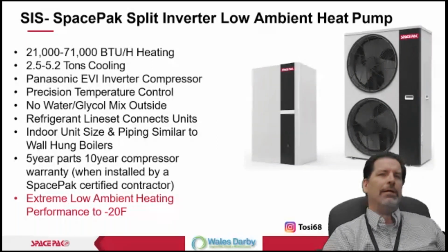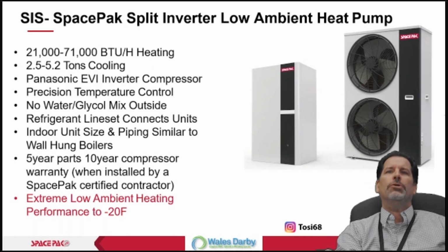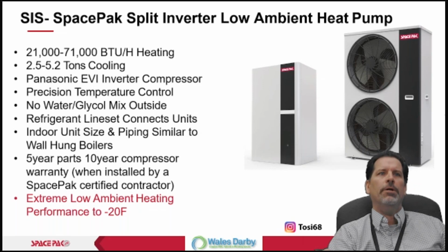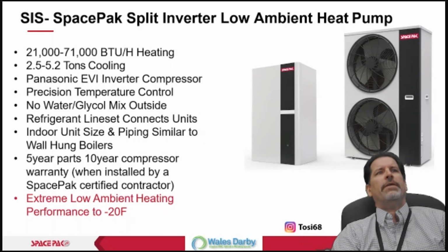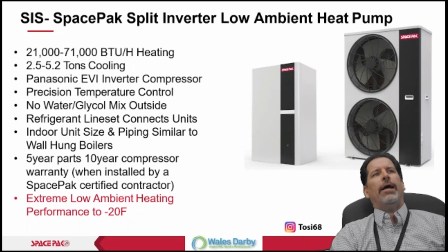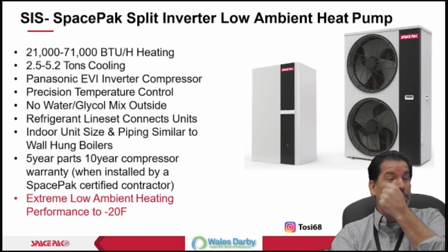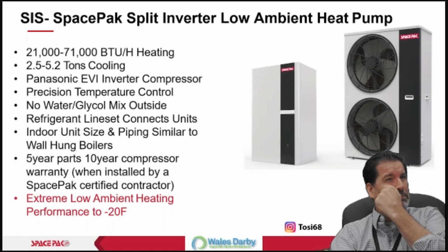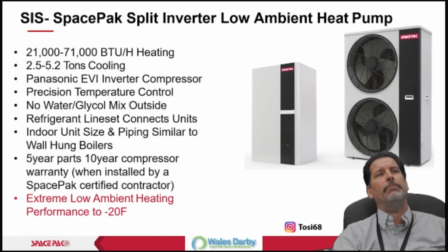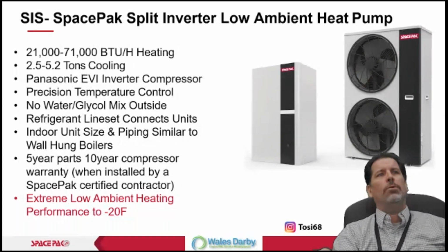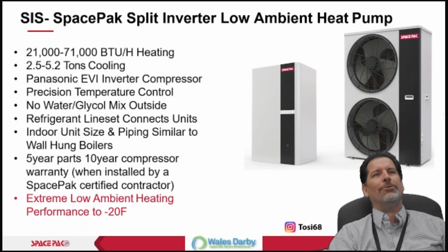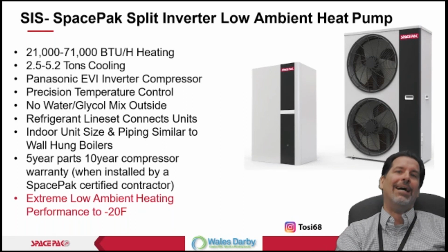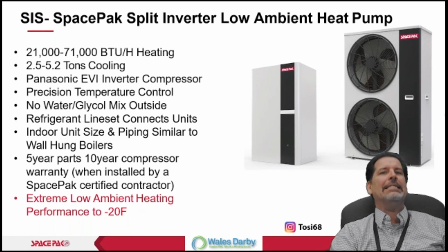Well, I asked the question, what are we delivering at -20 degrees? So there are some deeper dives into some of the spec sheets that we need based off of our design, our loads, right? But 21,000 to 71,000, 2.5 to 5.2 tons of cooling. This is a heater as well, so it is a heat pump as well. All right, no glycol. It says no water, no glycol mixture outside. Doesn't mean we don't need it inside though, because again, that refrigerant gets pretty cold.